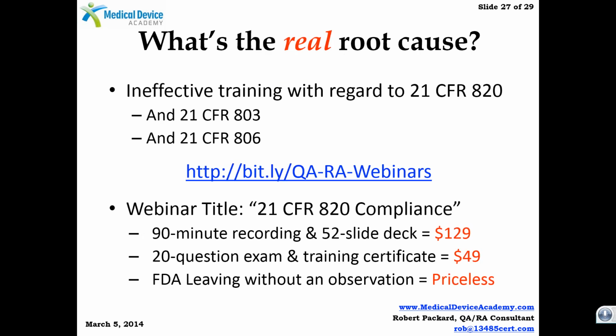We're nearing the end here. When you get a 483, one of the things that a lot of companies do is what they call a 5 why analysis. And I'm just amazed by how shallow their investigations are. They say, oh, I've got to change this procedure wording, so I changed the procedure to tell them to do what they didn't do, and I asked them to sign this training document that says they read and understood the procedure. Done. Isn't my CAPA effective?